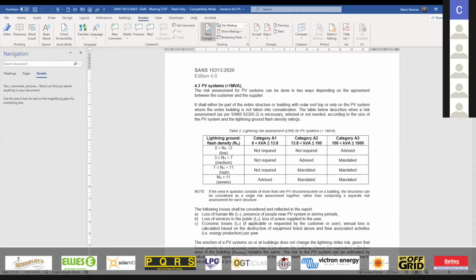Can you confirm we can see section 4.3, PV systems less than 1 MVA? Yes, we can see it. Here we say the risk assessment for PV systems can be done in two ways, depending on the agreement between customer and supplier: either a complete risk analysis, or the other way around, where people accept a residual risk per year, and you have to prove you're below that value.